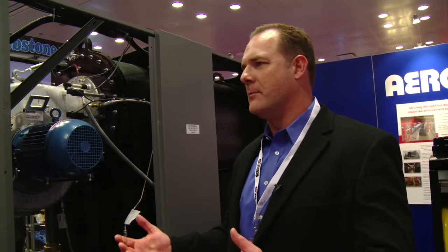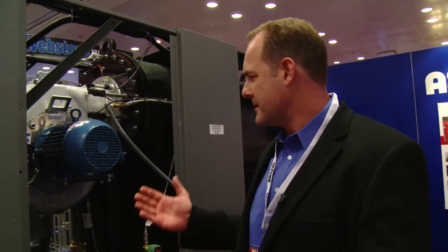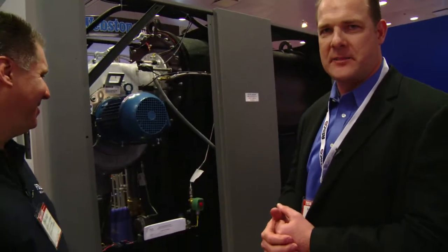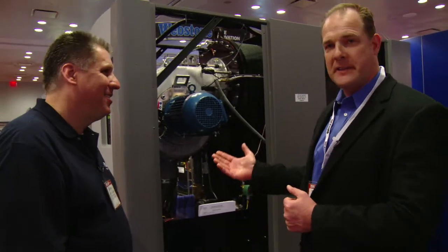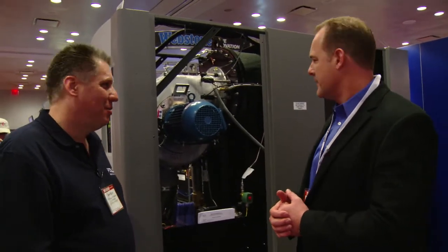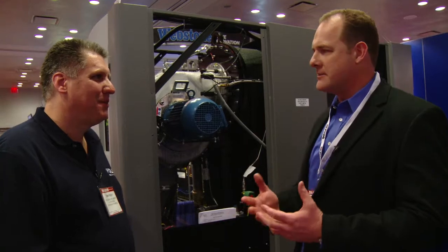I like that. Well, I'm a mechanical contractor by trade, and I get excited when I see all this heavy-duty equipment. What do you got over here? This is a beast over here. Tell me what you got over here, Harold. Actually, this is probably the smallest 6 million BTU boiler available in today's market. Wow. This is a fire tube stainless steel 6 million BTU boiler with a 15-to-1 turn-down ratio, which gives you a very high modulation capability, which is a huge savings in energy in today's heating applications.